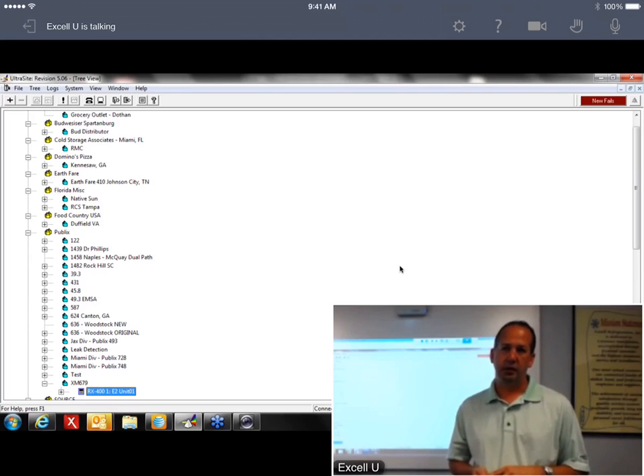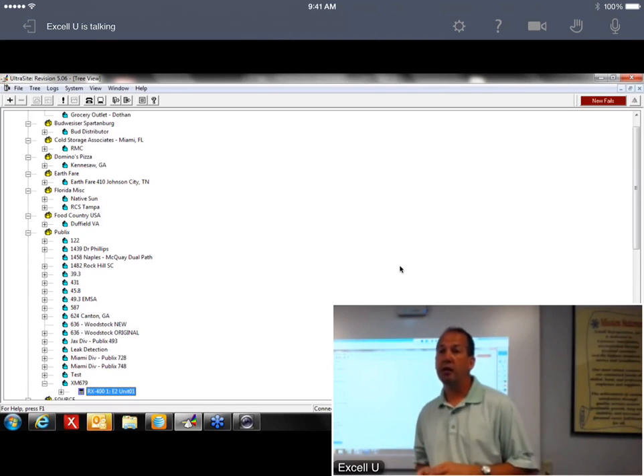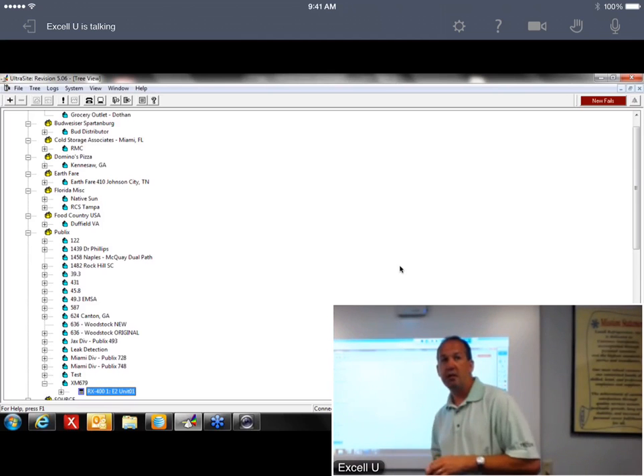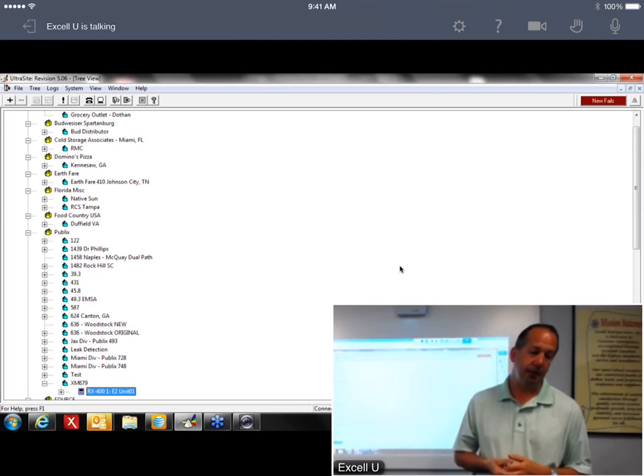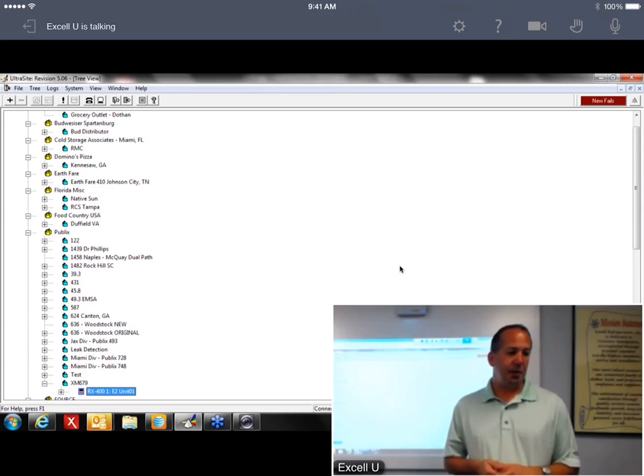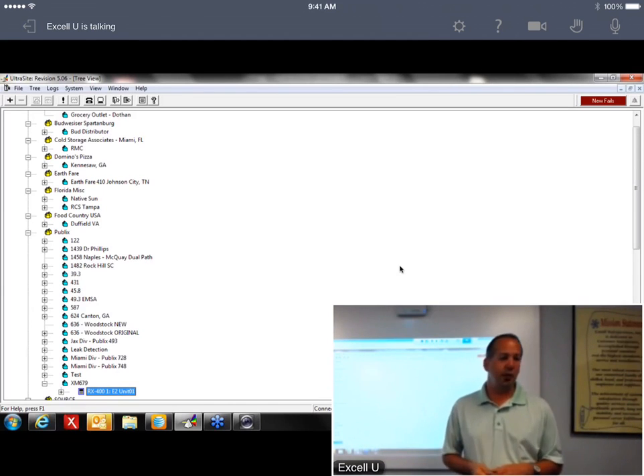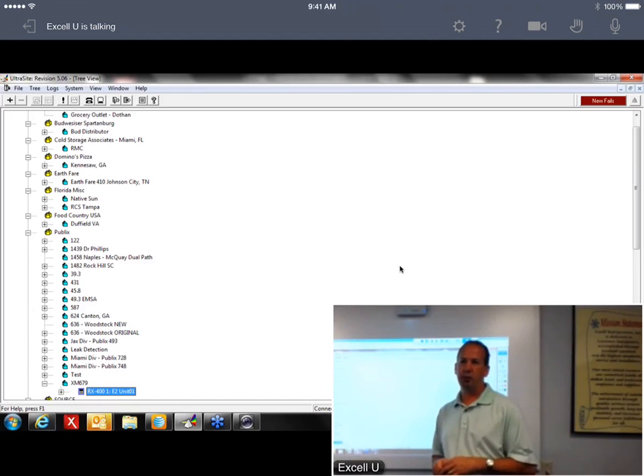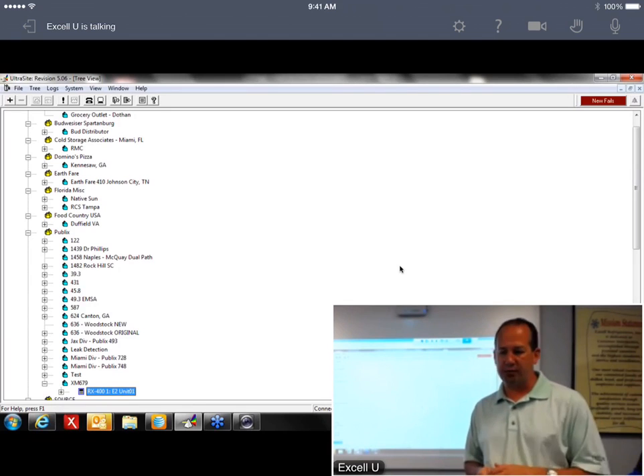It's almost like the Danfoss setup. Yes, it almost looks like it. A lot of people don't know that jumper's there, so I'm going to make sure everybody knows it's there. It's set for 120 volt because, like I said, that's what all the new cases are coming with. But usually the remodels will have a 24 volt coil, so you have to set that jumper if you're doing a retrofit.